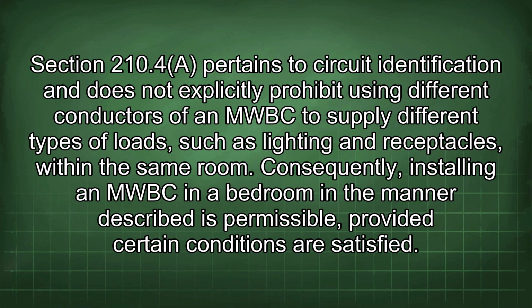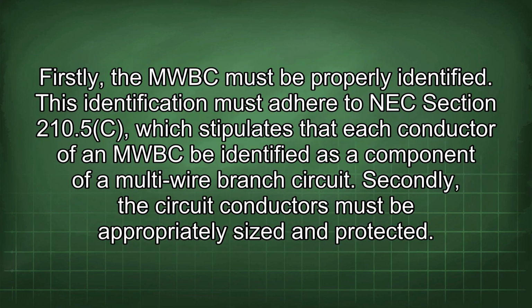Consequently, installing an MWBC in a bedroom in the manner described is permissible, provided certain conditions are satisfied. Firstly, the MWBC must be properly identified. This identification must adhere to NEC Section 210.5(C), which stipulates that each conductor of an MWBC be identified as a component of a multi-wire branch circuit.